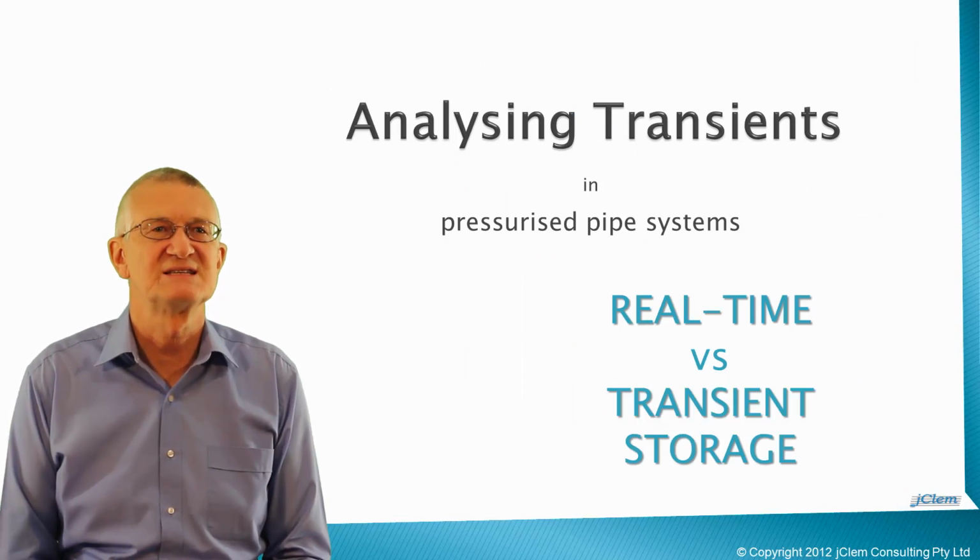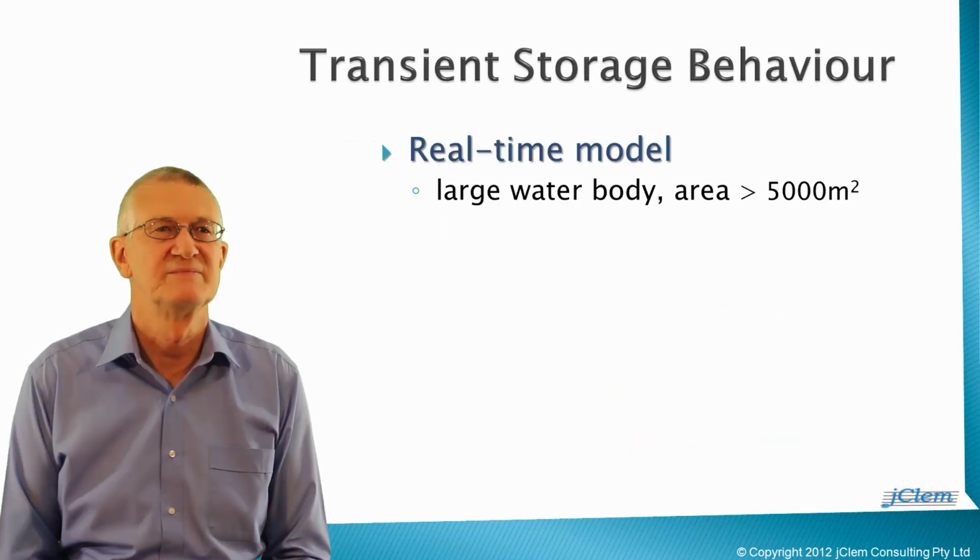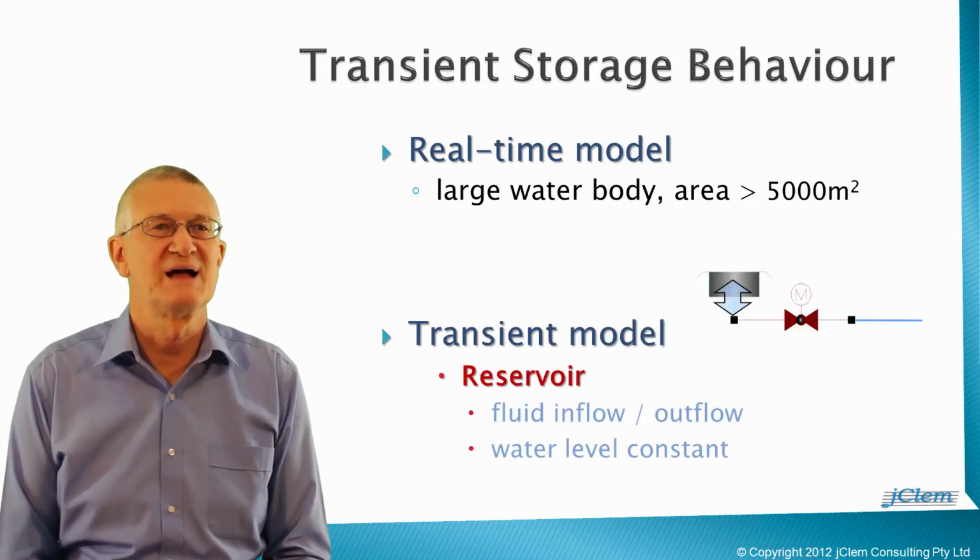Let me finish this lesson by describing how the WATHAM software handles any fluid storage during transient simulation, depending on the storage cross-sectional area. Users will notice some storage devices are handled differently between real-time steady-state analyses and subsequent transient analyses. A water storage with a cross-sectional area of 5,000 square metres or more will be modelled as a reservoir in transient simulations. A transient reservoir tracks the flow of water discharged into and out of the system.